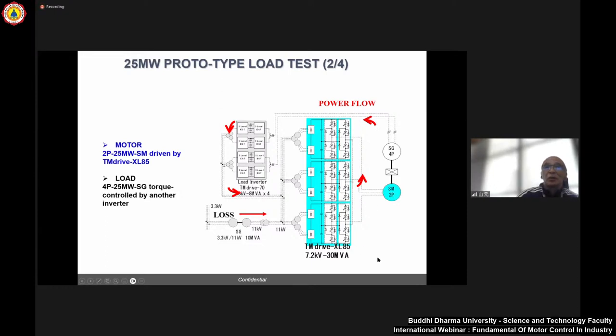So with this configuration, even though we import 20 megawatts, the actual power we need to apply to this line is very, very small, because we only need to supply the power loss of this portion, plus the synchronous motor loss and the synchronous generator loss. So no need to get a 20 megawatt power supply from here; only maybe 1000 kW is enough to drive the whole package, because the power we input to the motor and the power output from the generator back to the supply line is the same, except for power loss in the circuit. This is what we call back-to-back testing.